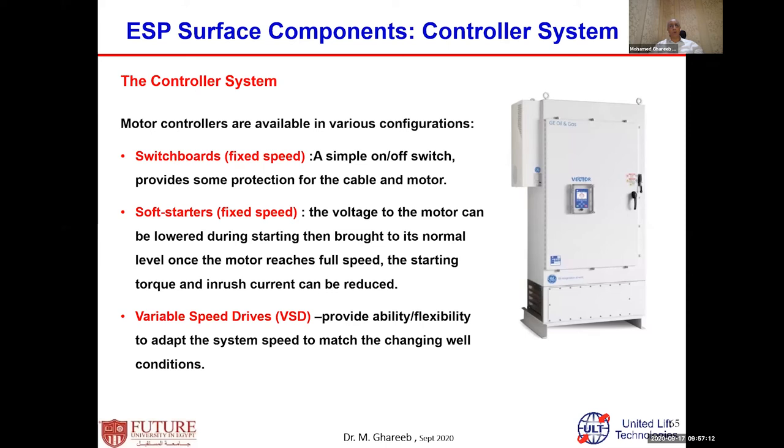We have another controller, what we call a soft starter switchboard. A soft starter with switchboard, like what? When I start any system, under any current conditions, look at the amps. The starting current is usually very high, because the starting torque for the motor, in order to move from static to dynamic, is very high.